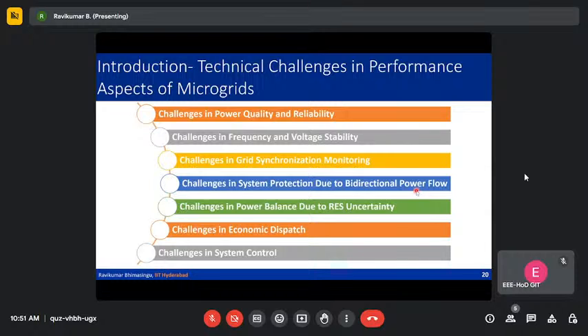This can be addressed quite easily in conventional systems where excitation controls are present. But whenever you connect energy sources to the grid through power electronics based voltage source inverters, as soon as there is a fault, they try to safeguard themselves and disconnect from the grid, which makes the system unstable.